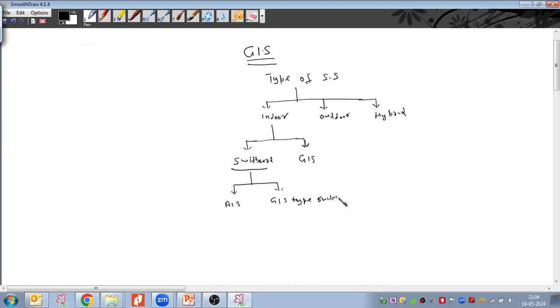Where the space at the substation site or any project site is limited, we go with the GIS type switchboard. For one panel, the AIS type switchboard generally takes approximately 800 millimeter to 1 meter width. When the space is limited and we want to reduce the panel width, we can go with the GIS type panel as well. That is also available and we use it in projects.